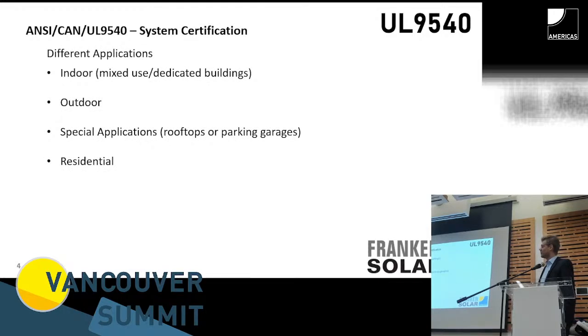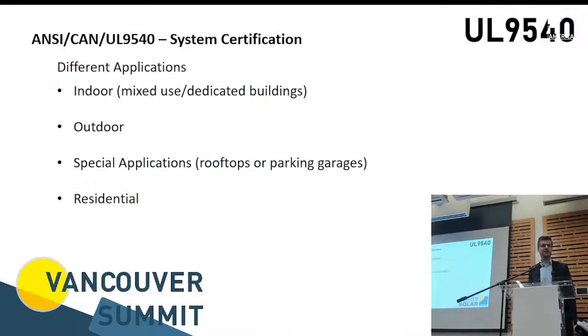Typically, the system certification has multiple categories. We have typically the indoor category for non-residential, let's say commercial applications or dedicated buildings like an e-house. We have complete outdoor systems that are in a special outdoor cabinet that you put outside of the building in regards to fire code and local requirements. Then we have special applications, which we don't want to talk about because that is, for example, for New York State. They have rooftop battery storage systems, or battery storage systems in parking garages to support EV charging. And then the focus we want to do today is the residential, because that's the most critical under that CEC 64900.